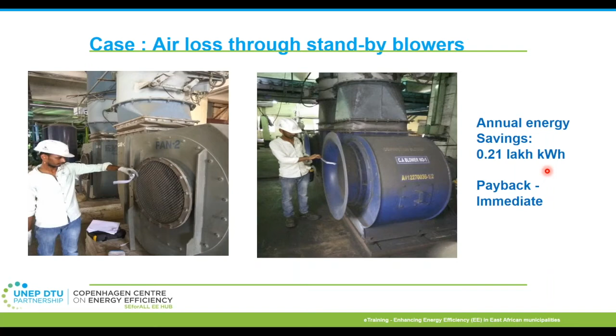What we observed is that fan number one was operating and fan number two was on standby, but part of the air being blown into the user side was actually returning back through a common duct or joint to fan two. That is nothing but wastage of energy. The simple fix was to close the common damper that separates the ducts between the two paths. Once closed, the problem was solved, and it was rectified immediately after we mentioned it. It's not much, but there is a significant amount of energy reduction.